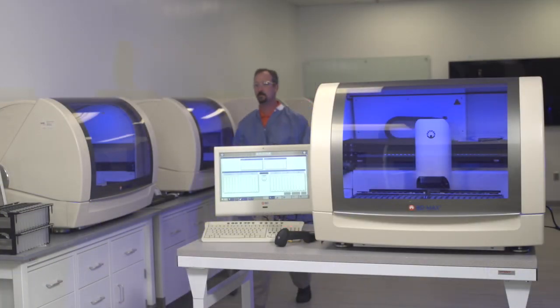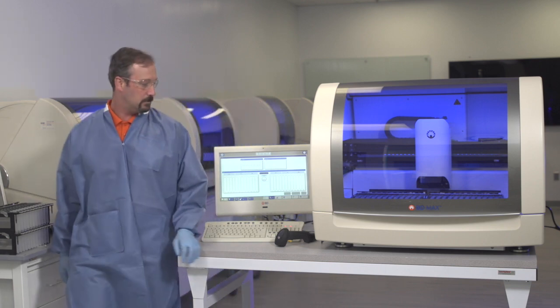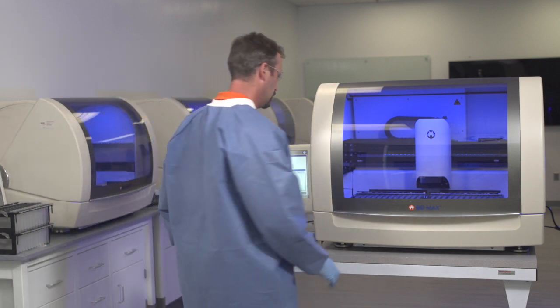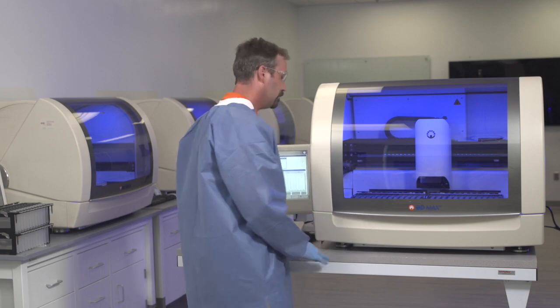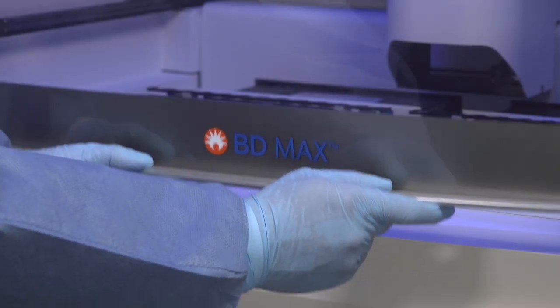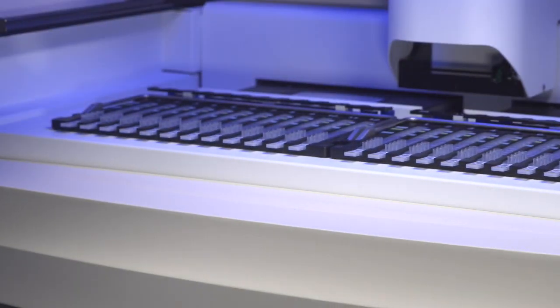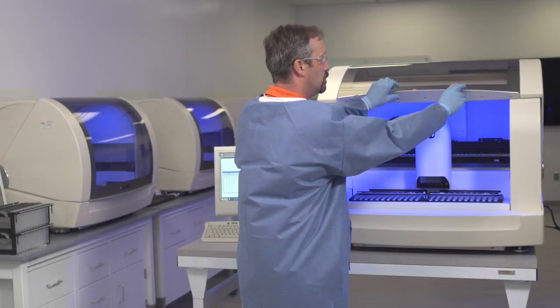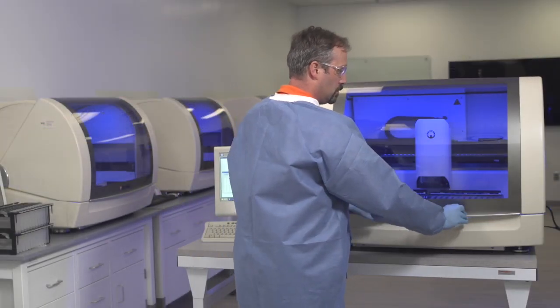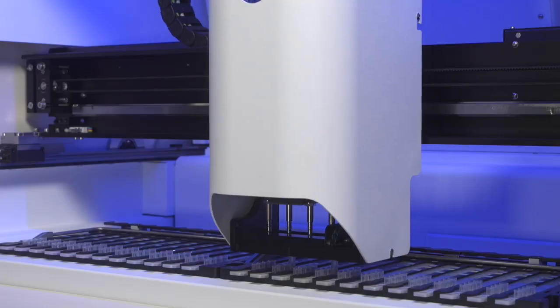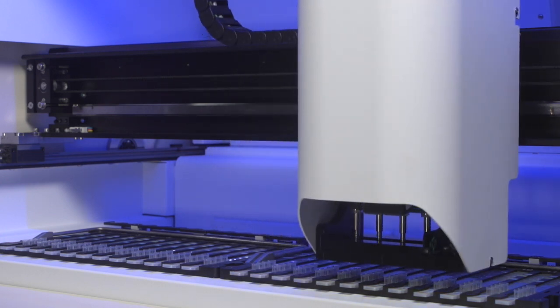The door can only be locked and unlocked using the BD Max system software. When unlocked, you can open it by grasping the handle, pushing down gently, and then sliding the door upward. Close the door by sliding it back down. When powered on, the instrument interior is illuminated. Under normal operations, the instrument light will be blue and indicates there are no active alerts. A flashing red instrument light indicates there are active or unacknowledged alerts that need your attention.